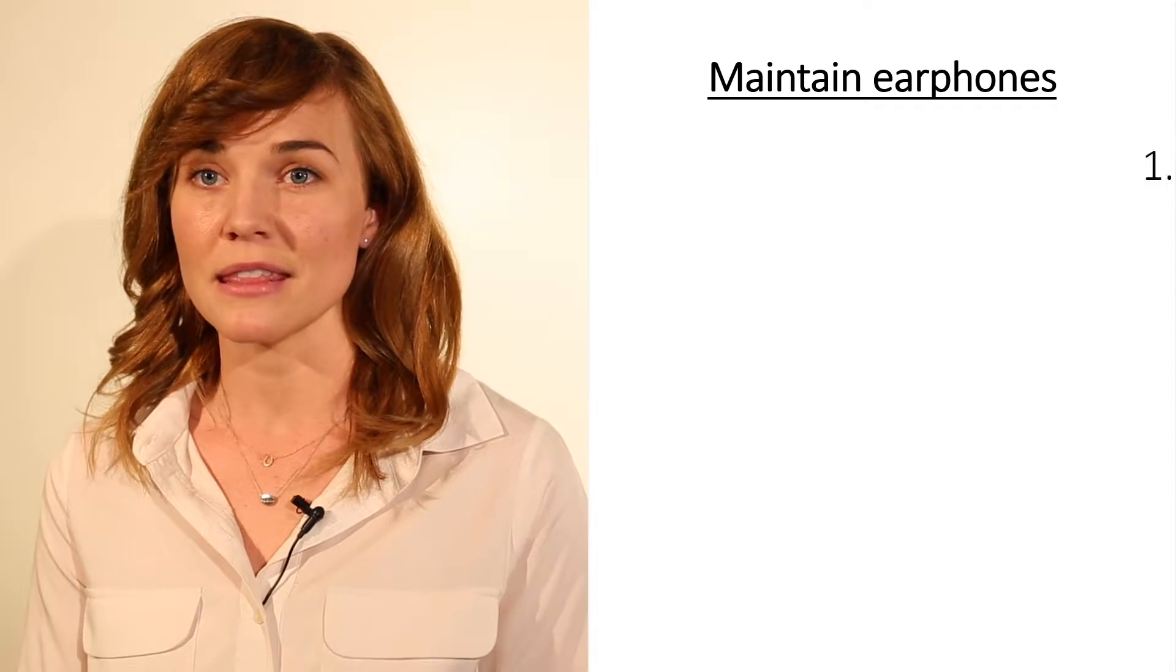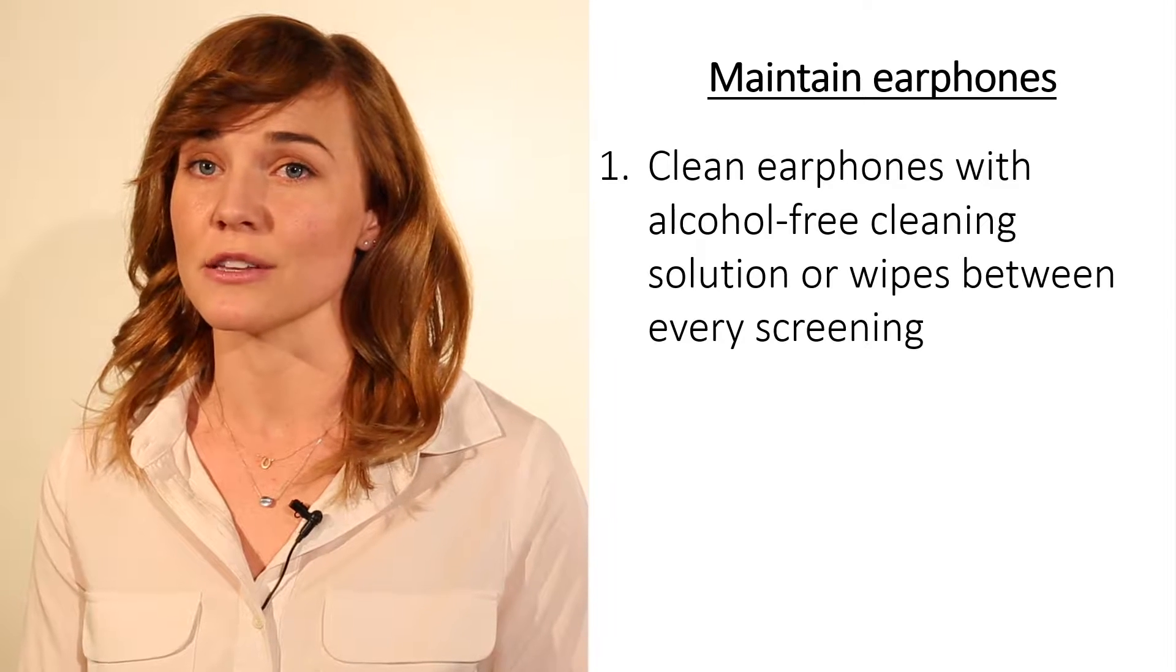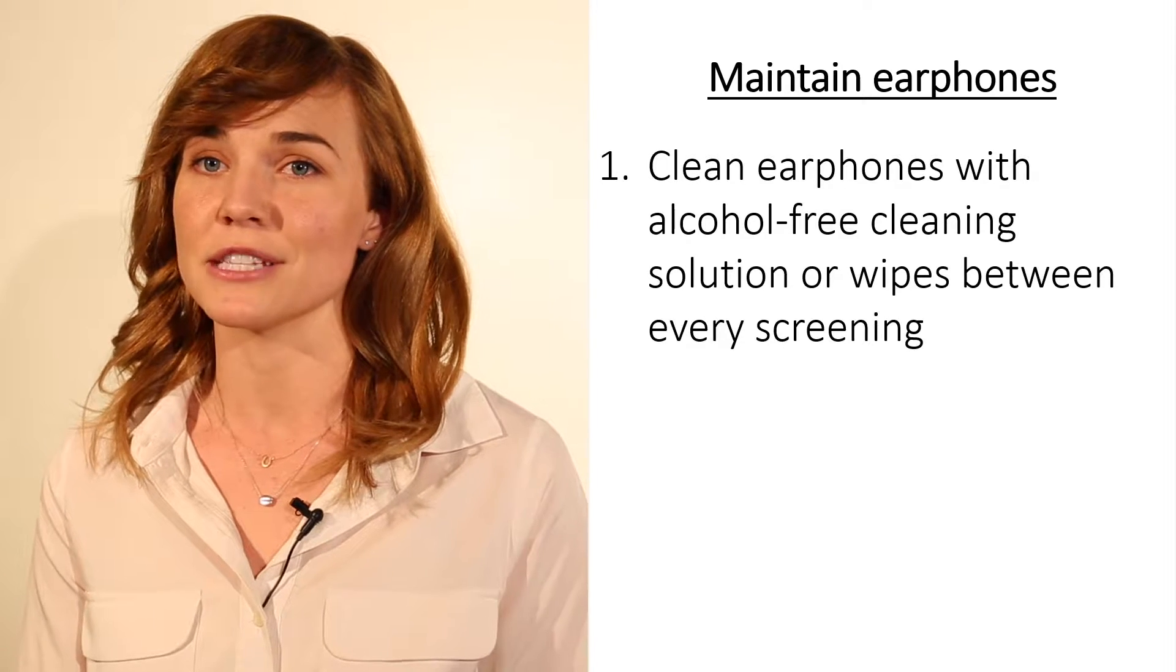Between annual calibrations, you should perform periodic maintenance for your audiometer. Clean the earphones with alcohol-free cleaning solution or wipes between every screening.